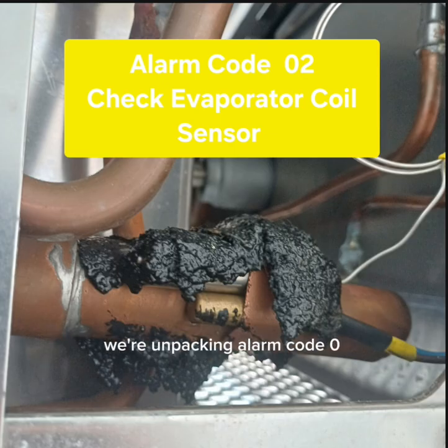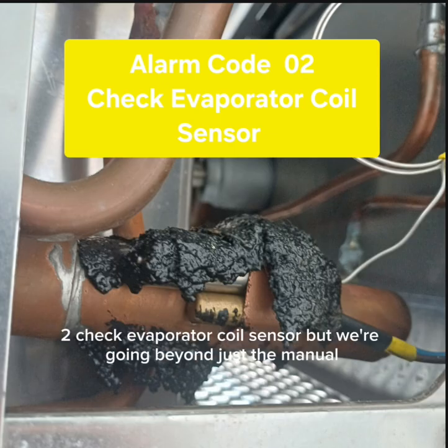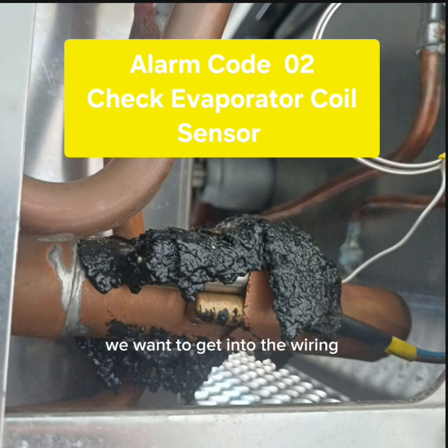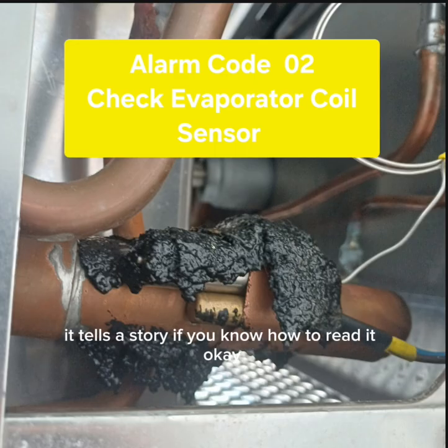We're unpacking alarm code 02, check evaporator coil sensor. But we're going beyond just the manual. We want to get into the wiring, the physics of why they fail, and the hidden logic the controller uses. It's fascinating because on the surface, it's just a temperature sensor, a little piece of plastic and wire. But the way the controller monitors it, the validity checks it runs, it's actually pretty sophisticated. It tells a story if you know how to read it.